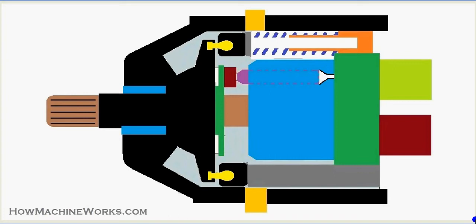So when we have a vertical swash plate at 90 degrees, there is no flow happening inside an axial flow variable displacement piston pump, but it becomes variable according to the swash plate angle when it increases or decreases. So how the cylinder block and piston rotate, let's see that. Here you can see it's rotating over here. The cylinder block rotates, so it's a single piston that I have shown, it's rotating, but there is no reciprocating motion for the piston because the swash plate is vertical, so there is no flow happening. And let's see the other part of it.